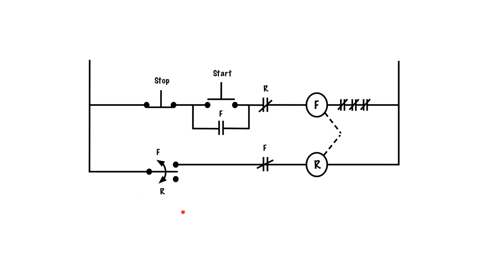This is our zero speed switch which works on centrifugal force. When the motor is going forward, it's going to throw this switch up into this position. If the motor has suddenly gone into reverse, it's going to throw it down into this position. So that's why we have this arrow—it's showing that there's centrifugal motion with the switch itself.